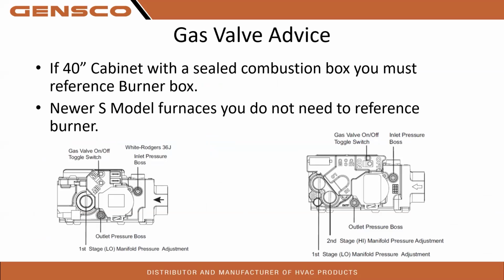If it's an older style with a barb, you're going to have to barb into it. These newer styles, you have the inlet pressure boss. So you simply loosen the screw. You don't have to remove it completely. And then place your hose over it, and you can pull your pressures from there.